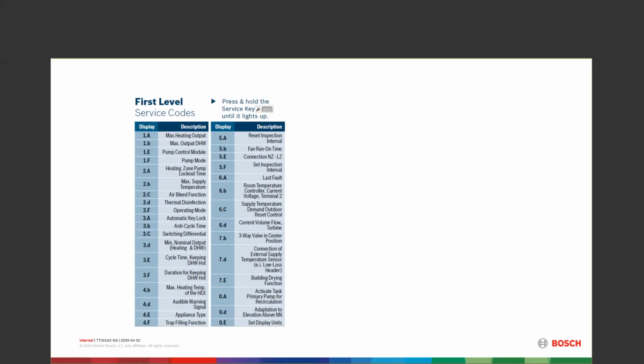1B will limit your domestic hot water maximum in the event you have a very low flow. Let's say we're only using 0.7, 0.8 all the time. Pretty easy to overcome that maximum, the domestic output going out to the faucet of 0.7, 0.8. So we can actually limit this down to 70%, 80%, 90% firing rate on your domestic hot water. Pump control module does that. Pump mode, you can change modes in the pump. These are all available in the book, in the manual itself.